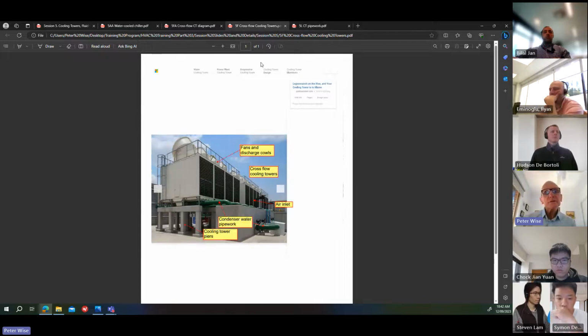You can use motorized valves to shut off when the system shuts down, and that'll hold the water back. Check valves will to a certain extent, but they can leak. So it's really important to keep the main runs of pipework down below the basin level of the cooling tower. And you can see it in this one as well.